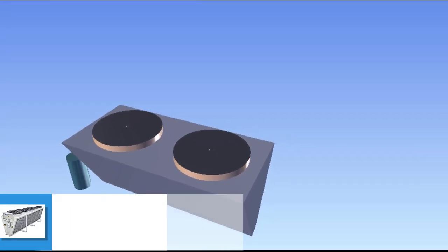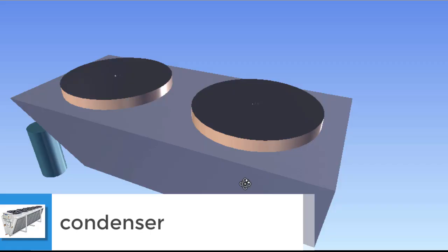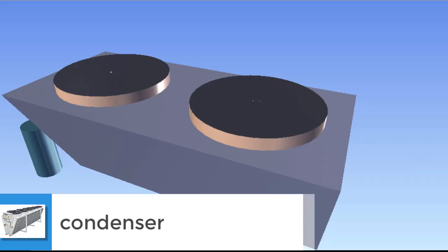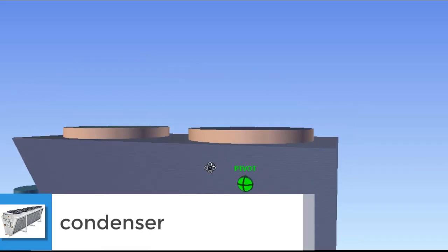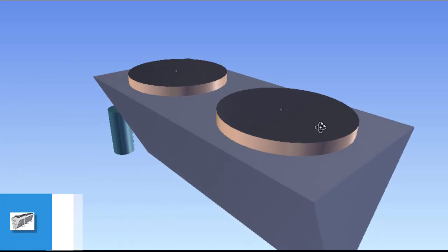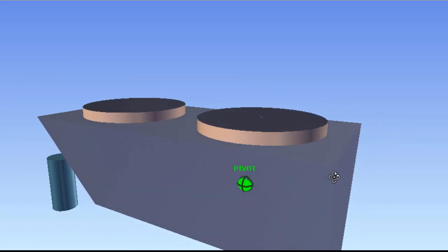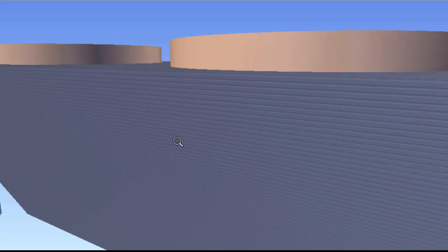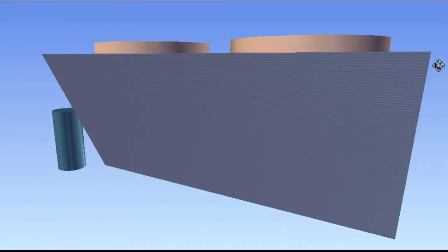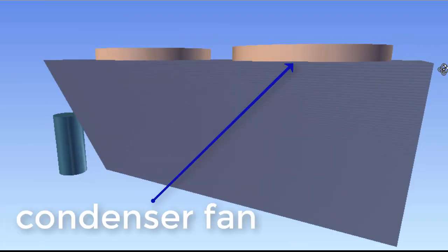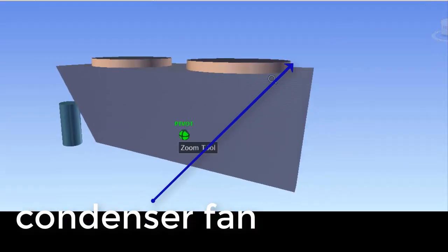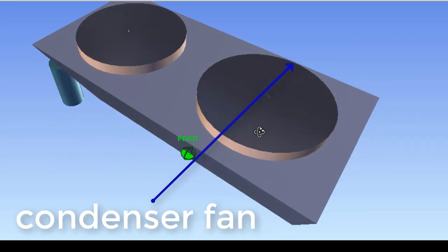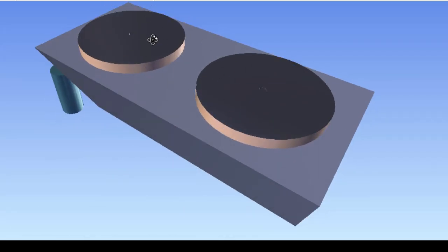The next component of the air-cooled chiller is the condenser. In the condenser, the refrigerant rejects heat to the surrounding environment. In the figure, you can see the tubes of the condenser. These tubes have gaps, allowing air to pass through, and this air absorbs heat from the refrigerant present inside the tubes. At the top, this is a condenser fan, which sucks in warm air and blows it out.